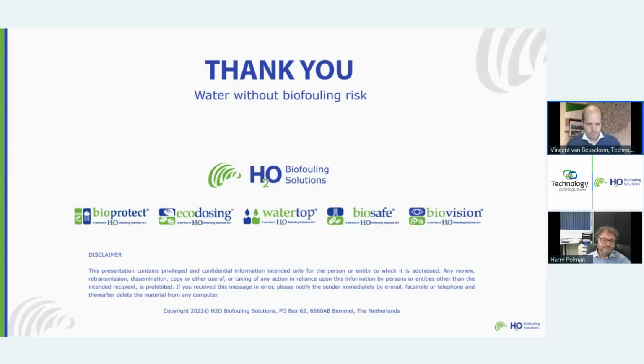And the other extreme: can it also be applied to freshwater systems? We also use it in freshwater systems, for example in the Netherlands, in rivers. It can be applied there too. One benefit we see in freshwater systems like in the Netherlands is that we reduce not just from continuous to intermittent dosing, but also tune dosing to the season. In the Netherlands, ecodosing is only applied 6 to 8 weeks a year to control biofouling in a freshwater cooling system, in a power plant, waste incinerator, and refinery, which we apply in that way. So the overall cost and impact of chlorination can be significantly reduced.